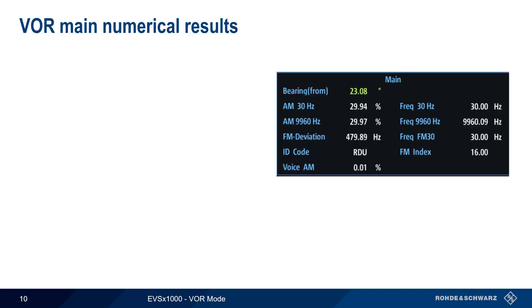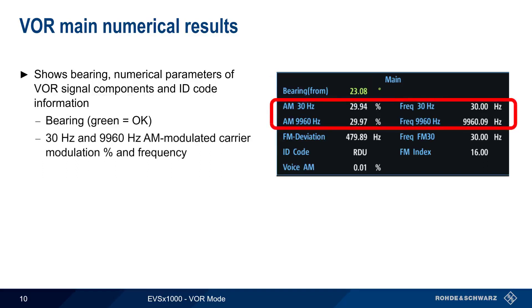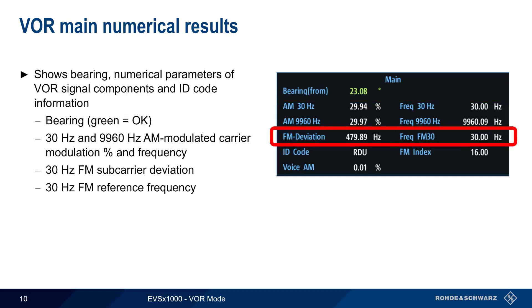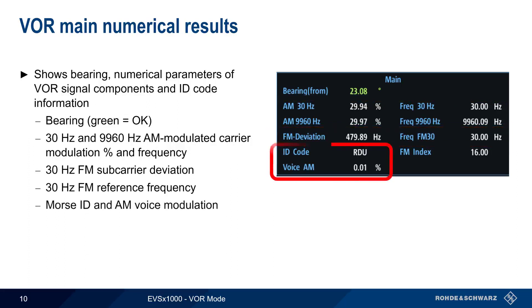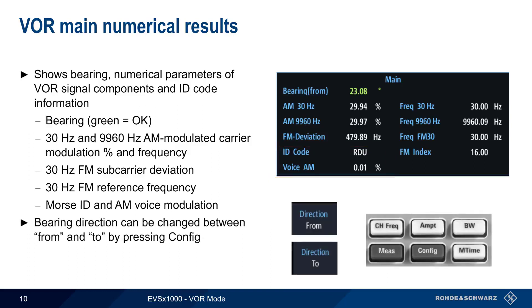The VOR numerical results view includes the derived bearing or radial, various numerical parameters of the VOR signal components, and information on the station's ID code. Bearing is shown in degrees, with green indicating a valid signal. The frequency and modulation for the AM signal components is shown, and both subcarrier deviation and reference frequency are given for the FM component. Parameters of the station ID, either in Morse or AM voice modulated, are also displayed. The bearing direction can be toggled between FROM and TO by pressing CONFIG and then selecting the desired direction.